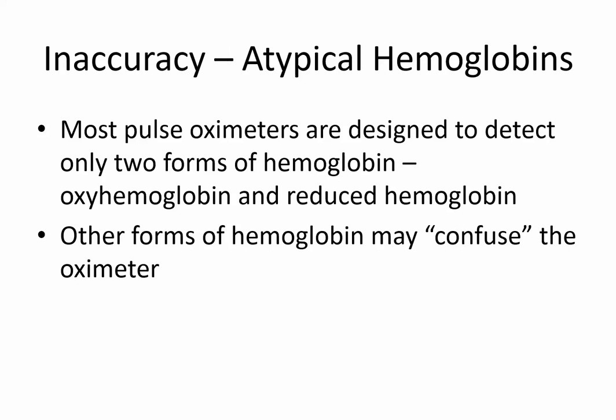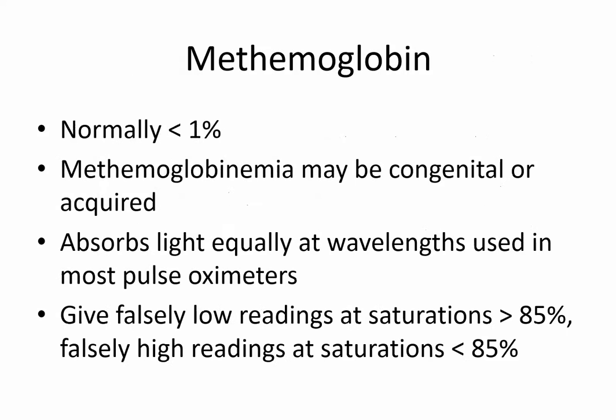Most pulse oximeters are designed to detect only two forms of hemoglobin, oxyhemoglobin and reduced hemoglobin. Other forms of hemoglobin may confuse the oximeter. Let's talk about some of those aberrant hemoglobin forms. Methemoglobin is normally less than 1%. It absorbs light equally at the wavelengths used in most pulse oximeters. Therefore, it effectively defaults to a saturation of 85%. That means that it's going to give falsely low readings at real saturations greater than 85%, and falsely high readings at saturations less than 85%.